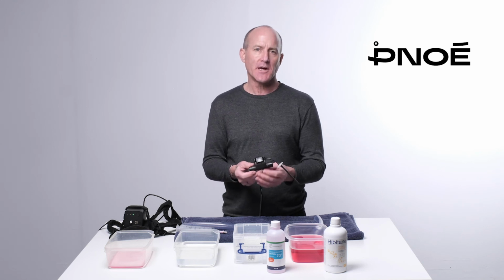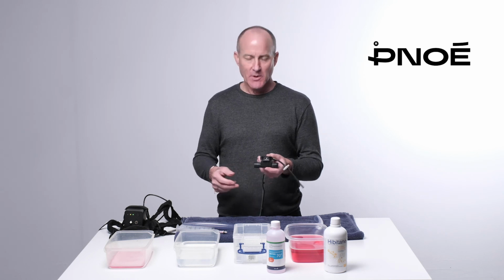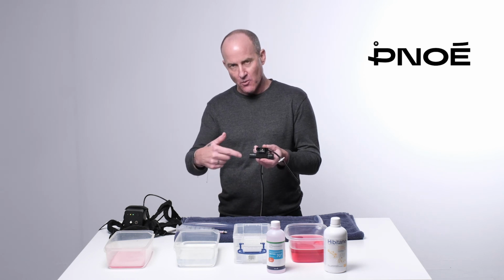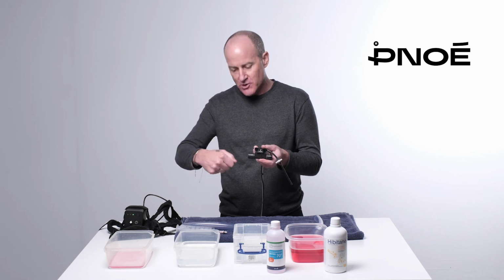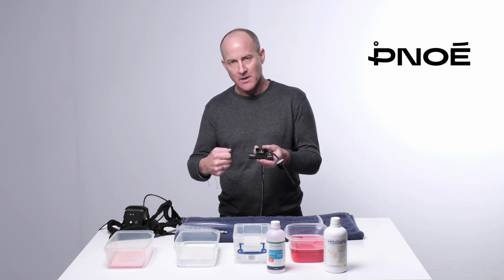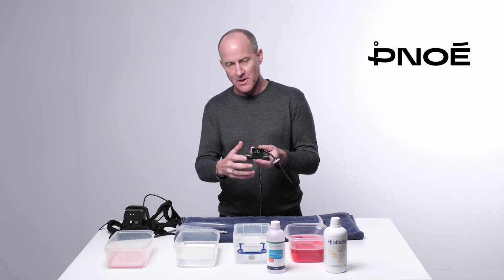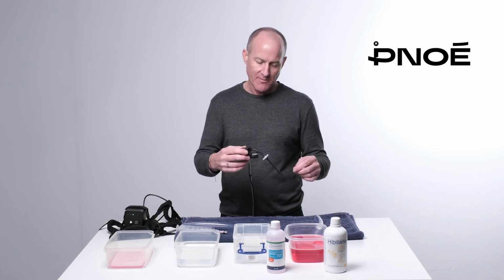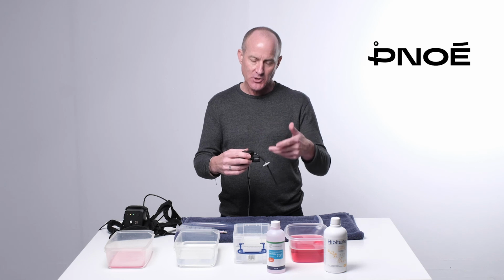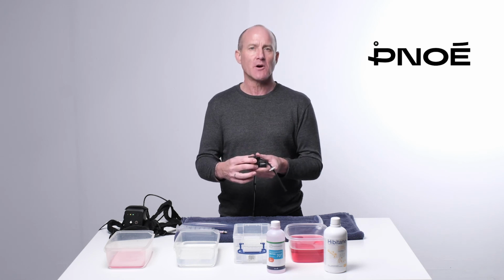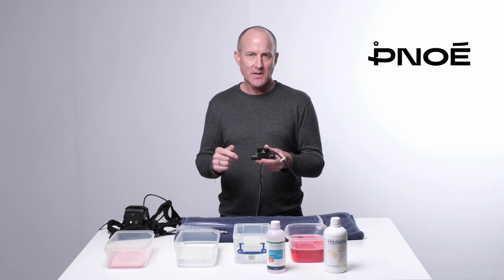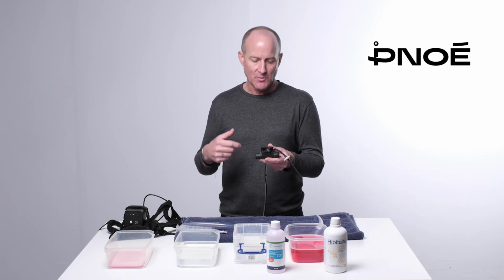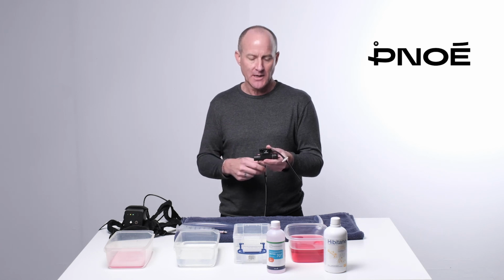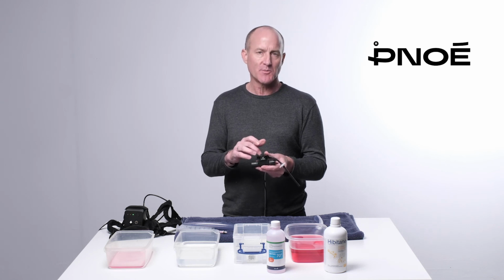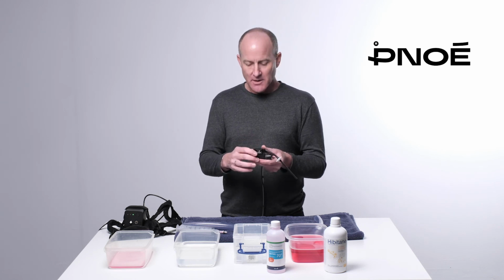Or you can use a hair dryer on a cool setting, in which you would blow air through one port for 5 minutes, making sure that you're angling the hair dryer to get into all parts of the flow sensor, and then 5 minutes through the other port to make sure all the internal compartments are completely dry. The hair dryer method is the best method if you plan on testing and retesting throughout the day, to ensure that your flow sensor is completely dry on the inside and therefore have accurate measurements.